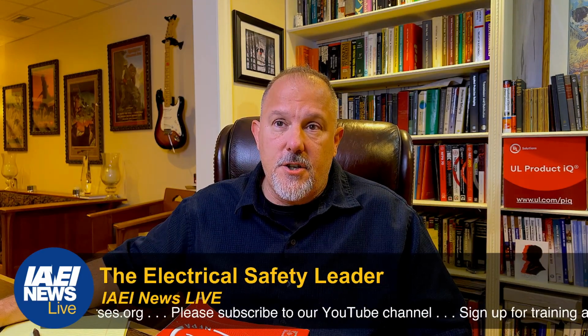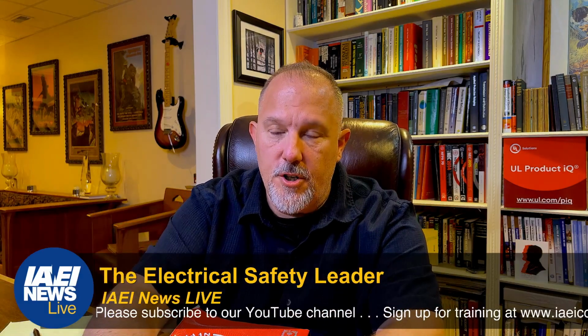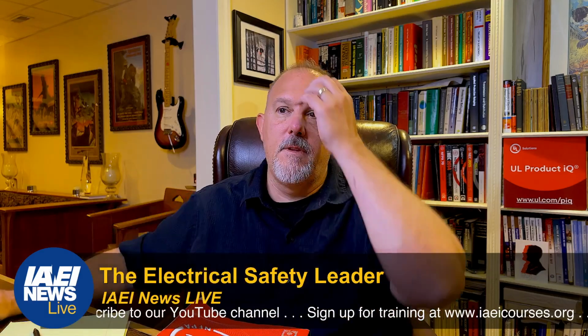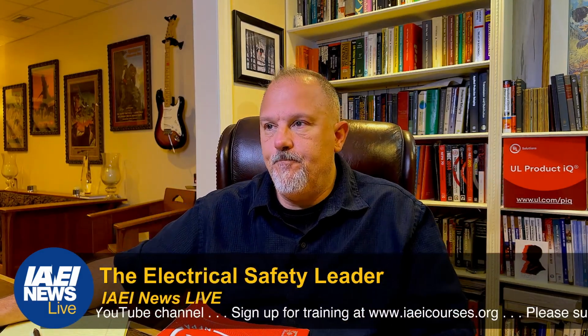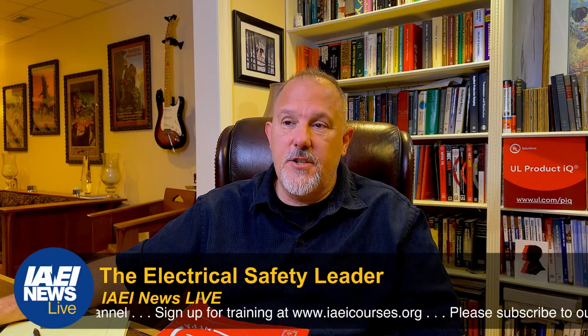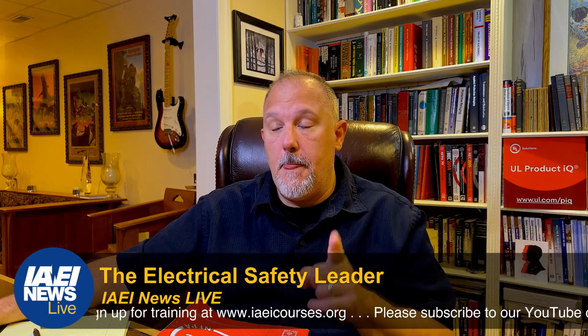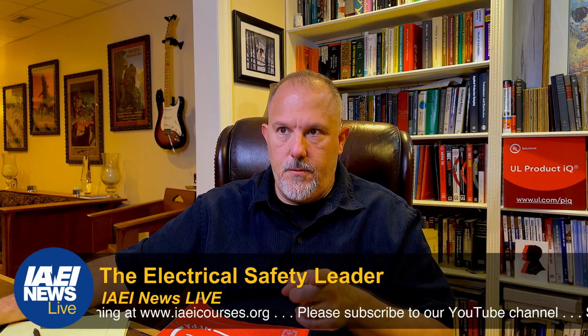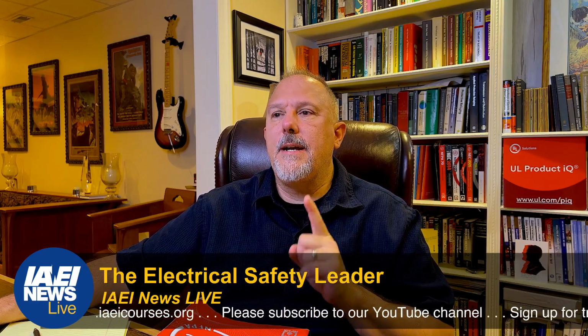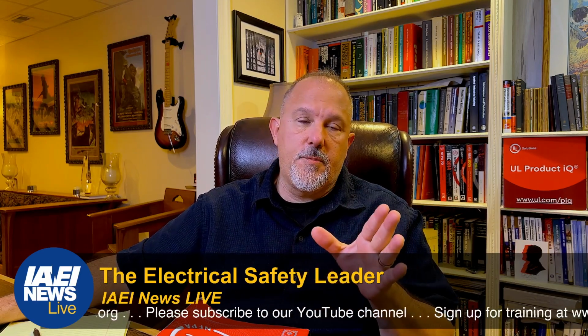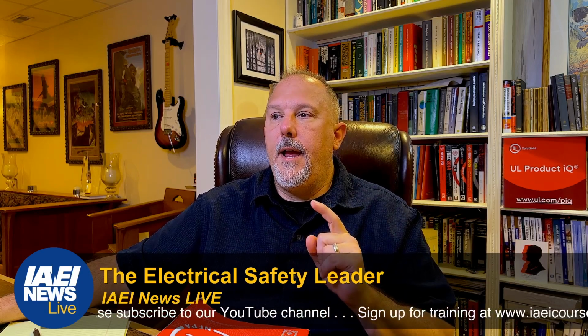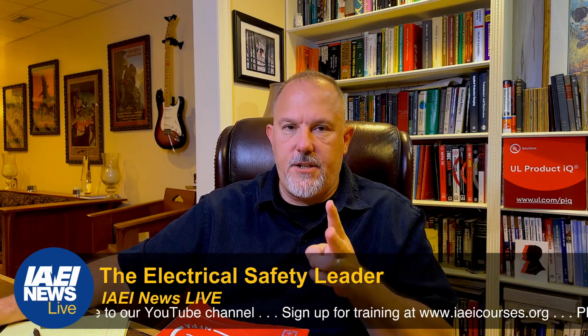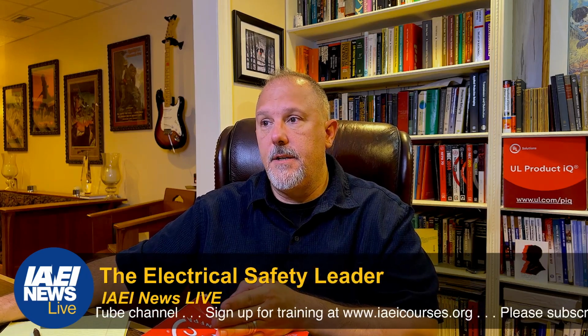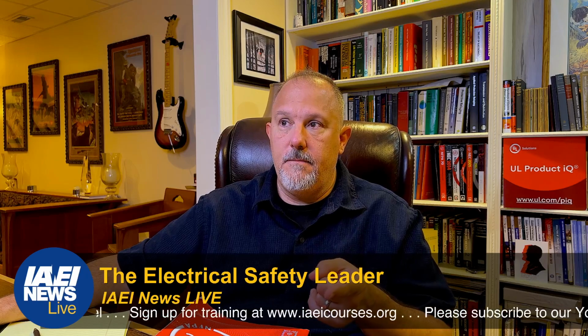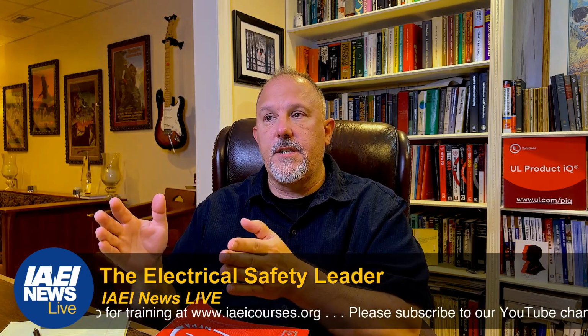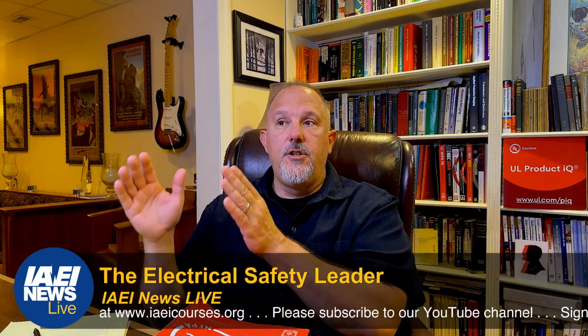Now let's do this. Let's search all of NFPA 70 for surge arrestor. And it's an ER, not an OR. So we find it in 242, obviously, because 242 is for surge protective devices. Article 242, this is an interesting thing. Article 242 is titled what? Overvoltage protection. And there are two types of overvoltage protective devices. One is a surge protective device, and the other is a surge arrestor. And 242 tells us that surge protective devices and surge arresters shall not be reconditioned.